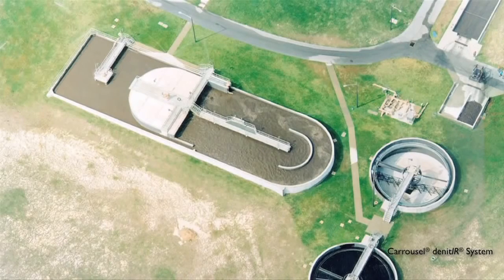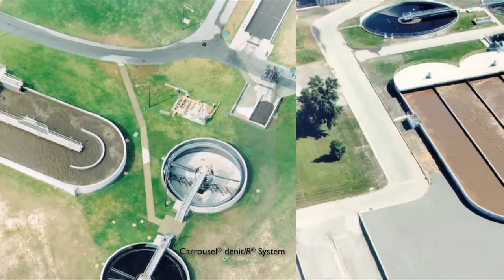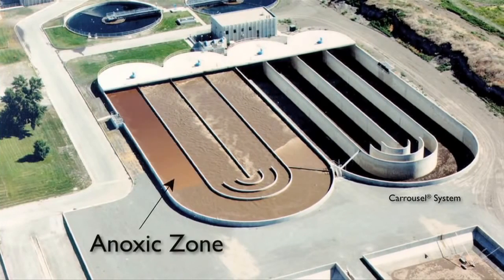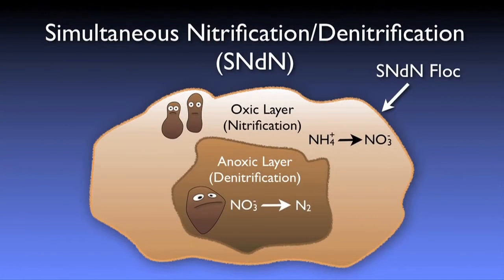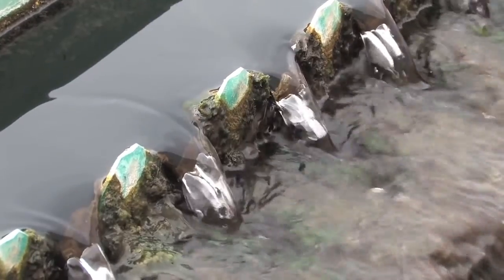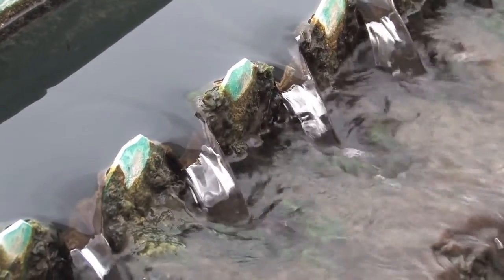There are many alternative strategies for developing anoxic conditions. Some treatment plants are designed to have dedicated anoxic zone volumes in the flowchart, while others strive to develop these anoxic zones within the oxidation ditch or aeration zone by rigidly controlling aeration or by turning off aerators for set periods of time. Additionally, under certain conditions, microanoxic zones can be developed within the bacterial flocs themselves, resulting in what is referred to as simultaneous nitrification-denitrification. Various levels of denitrification may be required depending on the local discharge permit. However, full biological denitrification typically results in only 1 to 3 milligrams of nitrate in the effluent stream.